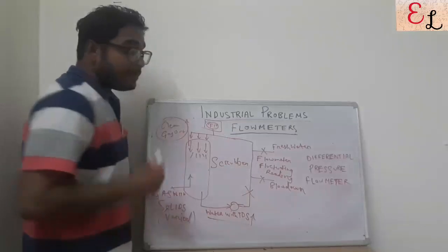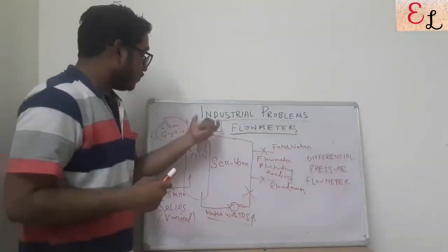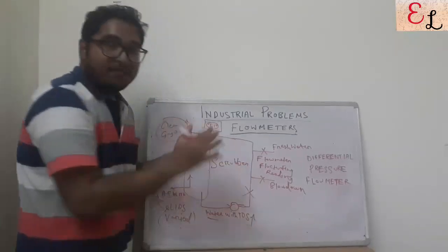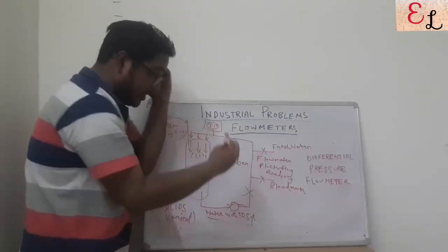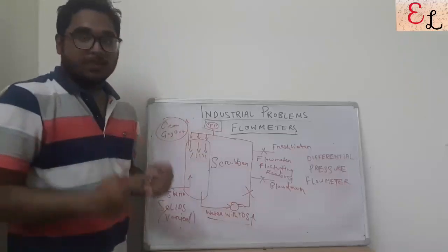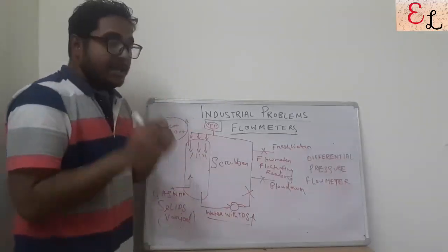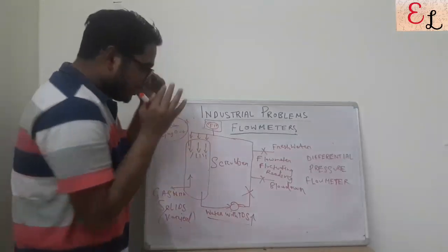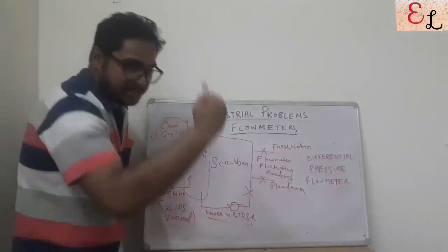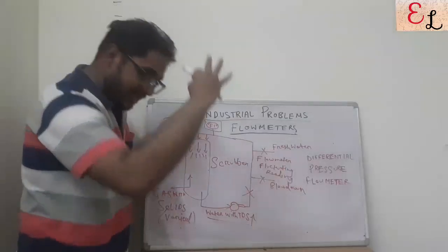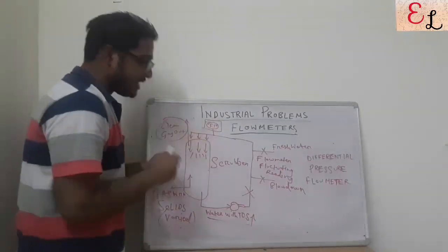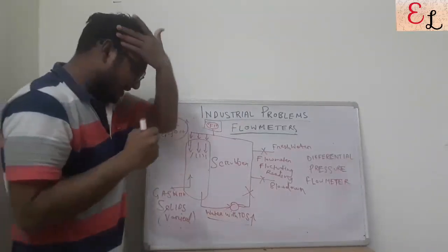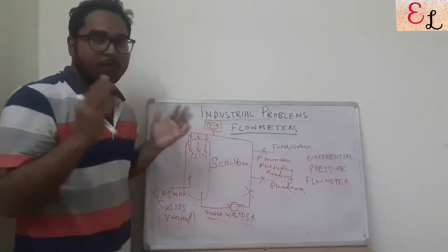So there has to be something wrong with the process parameter because of which the flow here is fluctuating, whereas we have set the valve openings the same throughout the process, but the flow is steadily changing. It's not steady, it's changing throughout the process. First the flow is decreasing, then the flow is suddenly increasing, and then again slowly decreasing. So what is happening? Why is there a very varied flow rate in the system? Why is the FIT showing a varied flow rate?